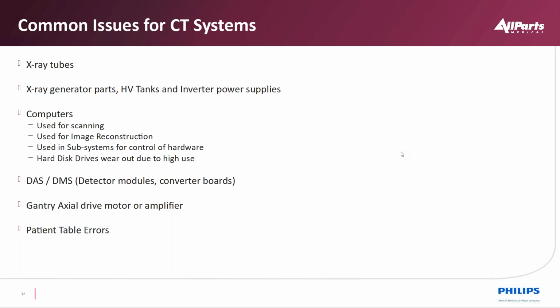And then we have detector modules. Crystals do not like radiation. So one of the things that happens over time is the center detector elements tend to go first because they get more X-ray, and those modules degrade over time. Once they degrade at a certain rate, our image CT number attenuation coefficients are hard to detect, and so we'll wind up replacing those defective modules and then recalibrating the machines.